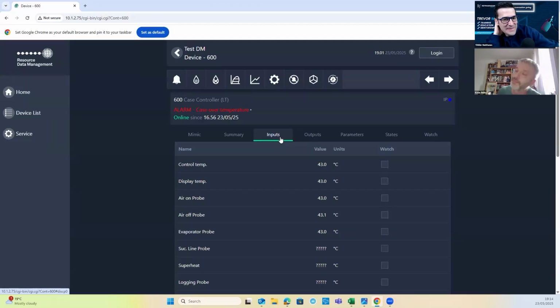So I'm immediately thinking when I see that, am I on the right range of probe? Because RDM supports a multitude of different probe types. Read the manual is what I would advise on that, and just check your probe types. There is a menu called Unit on the RDM controllers, which lets you change that probe type. You can do it through the buttons. If you're connected directly to the controller, you can do it through the network. Everyone is going to do it through the buttons, realistically.